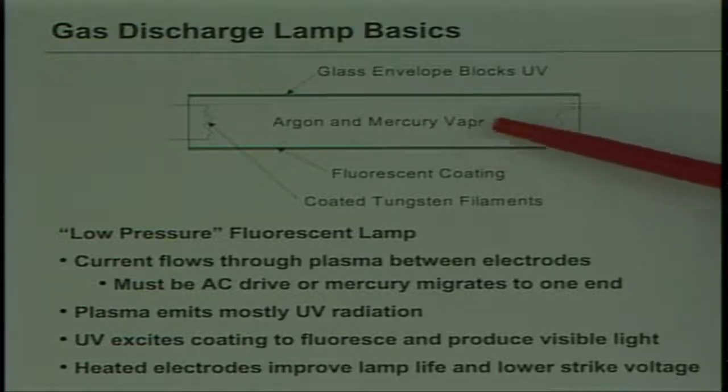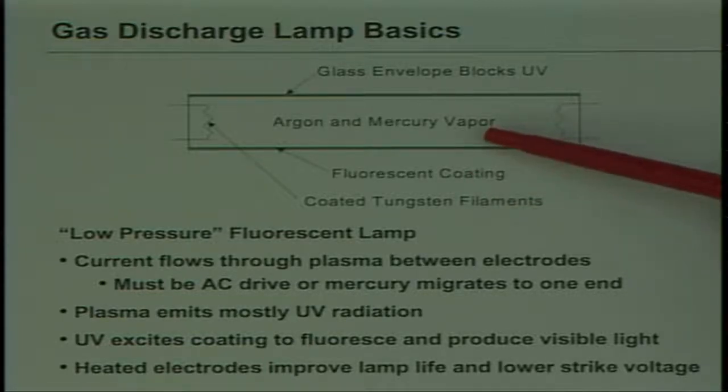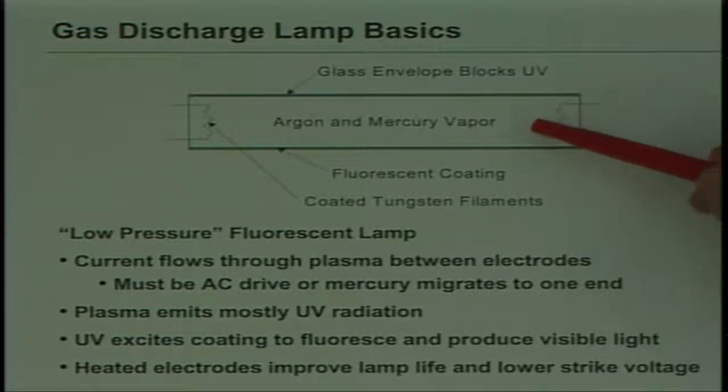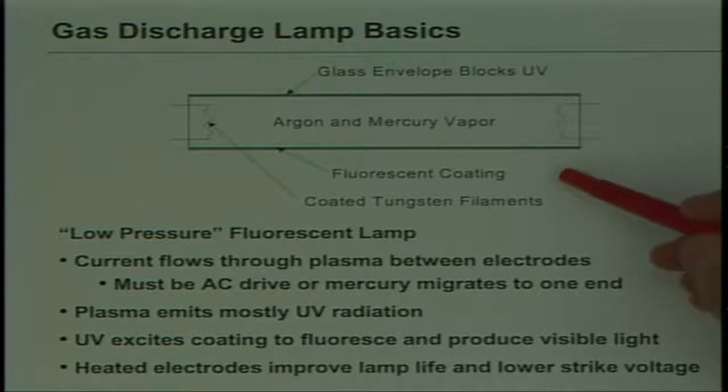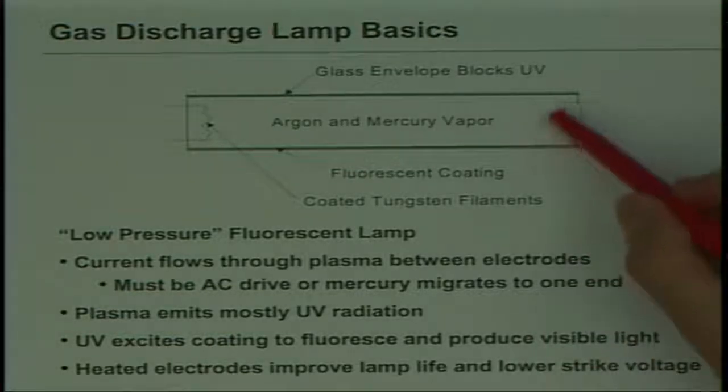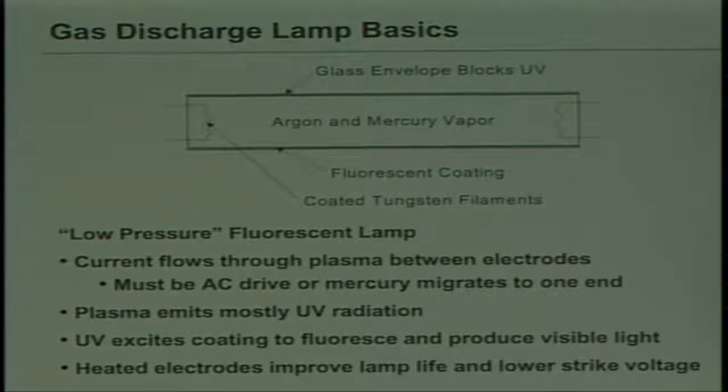That's the gas inside. When you excite that, you create a plasma, and the fluorescent coating is actually what produces the majority of the light. The plasma generally produces ultraviolet radiation, and that is what's used to then excite the phosphor. On each end, there are these tungsten filaments. Some lamps have just simple electrodes, but the filaments give the advantage that you can preheat them and it lengthens the lamp lifetime.